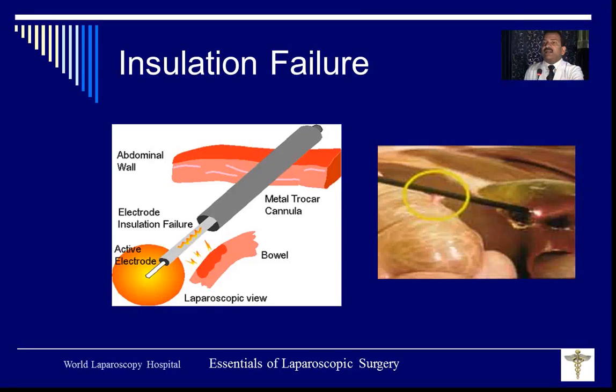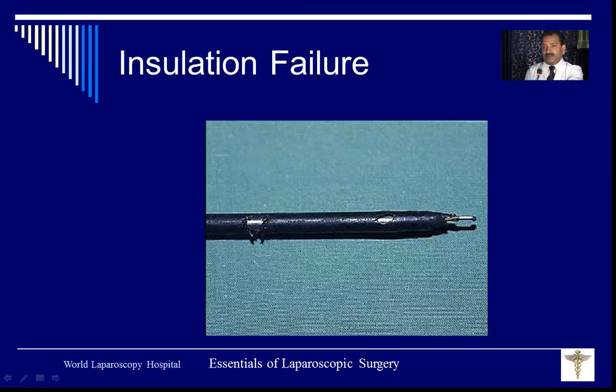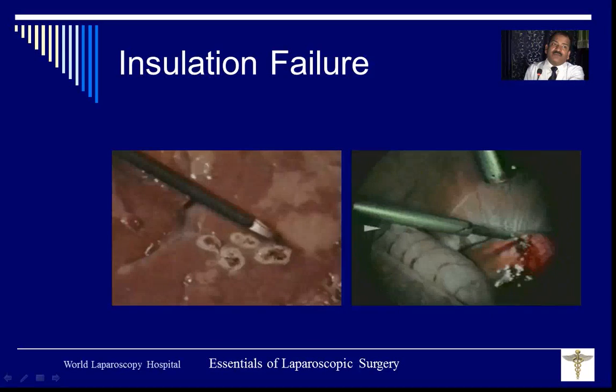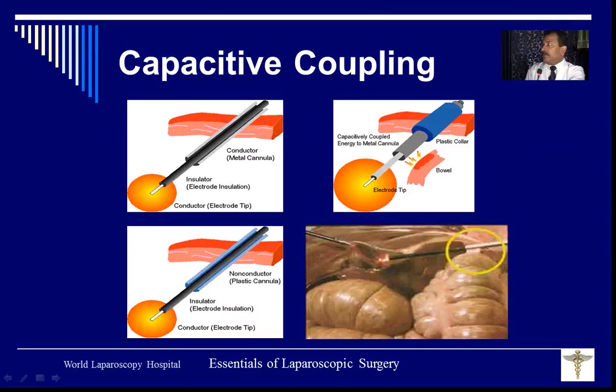Then the problem of electrosurgery can be minimized. Never activate it in an open circuit. And this type of insulation failure should be regularly checked.